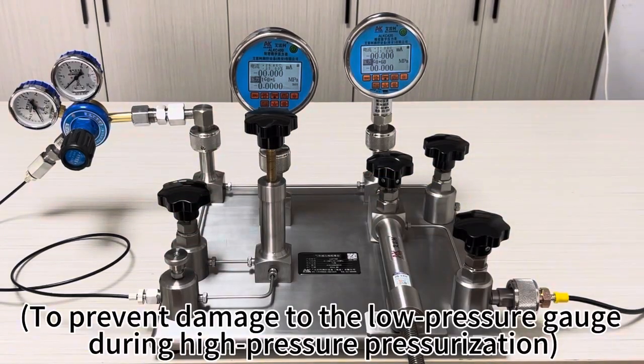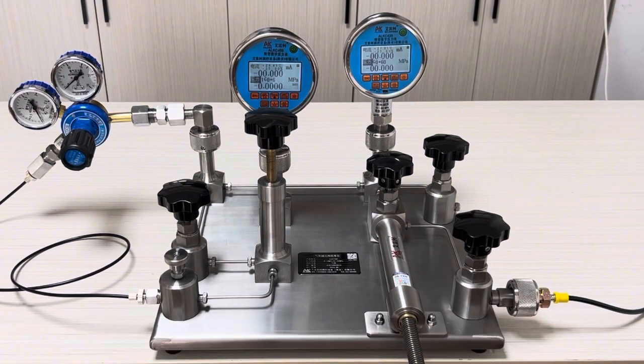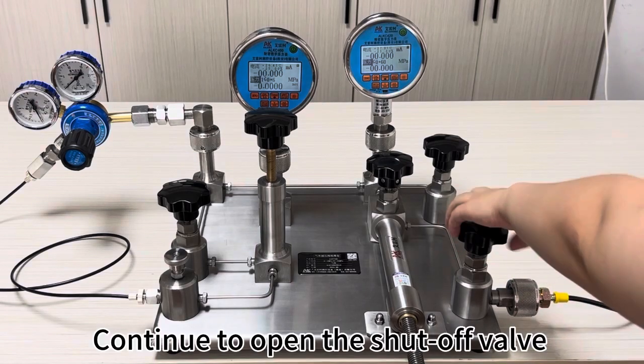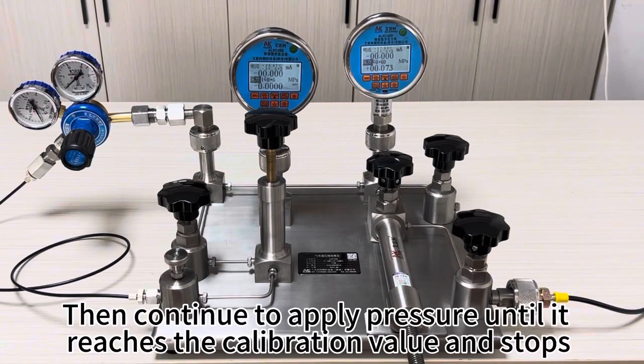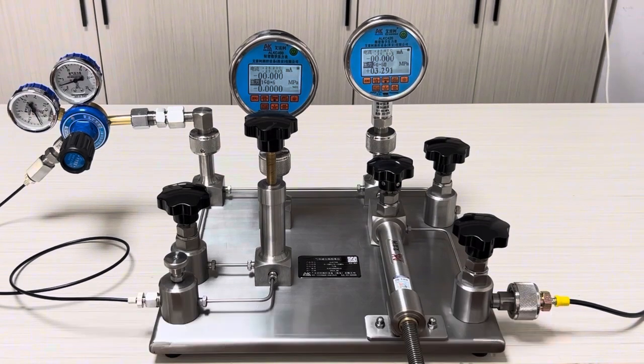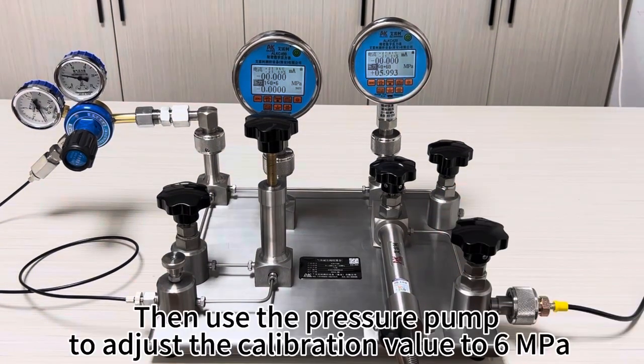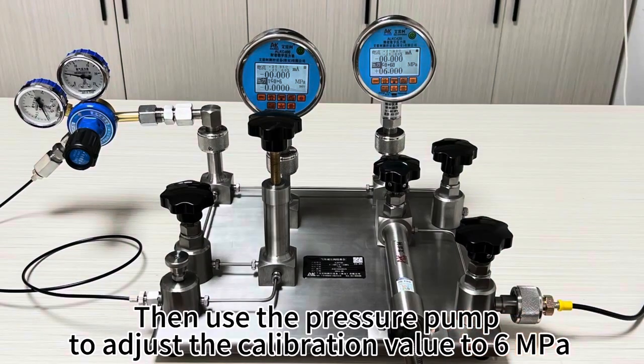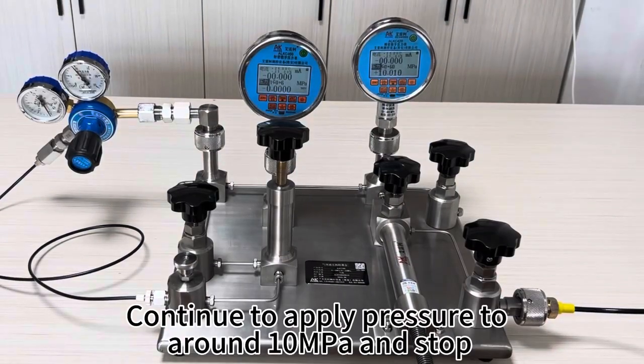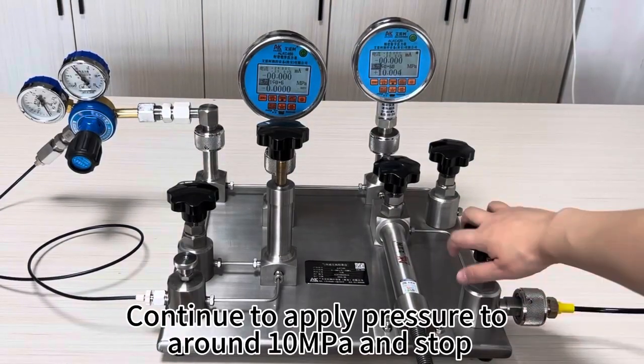To prevent damage to the low-pressure gauge during high-pressure pressurization, continue to open the shut-off valve. Then continue to apply pressure until it reaches the calibration value and stops. Close the shut-off valve again. Then use the pressure pump to adjust the calibration value to 6 MPa. Continue to apply pressure to around 10 MPa and stop.